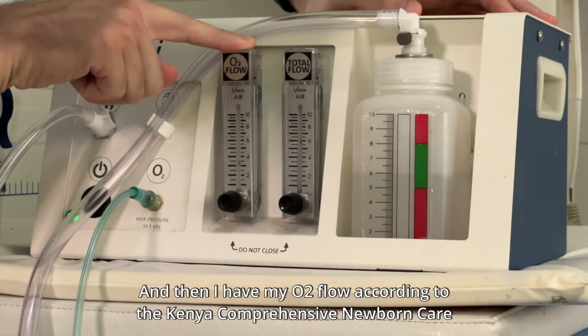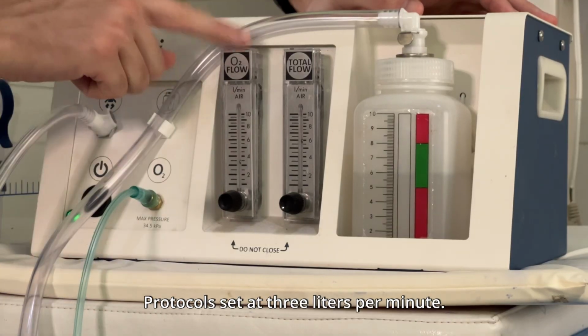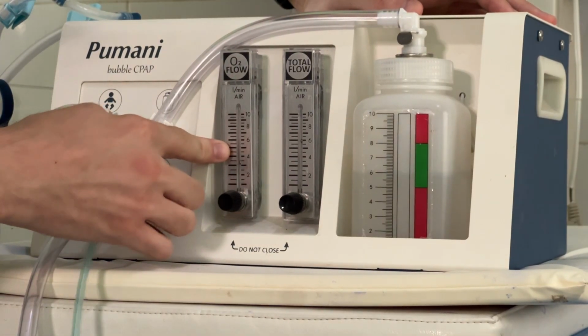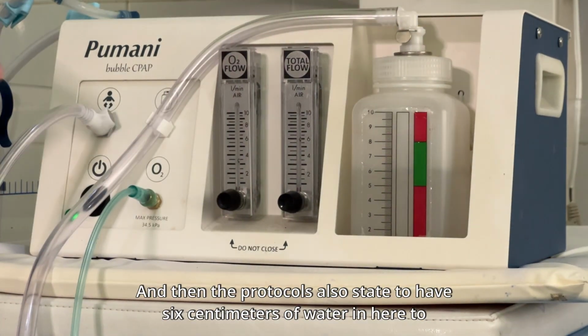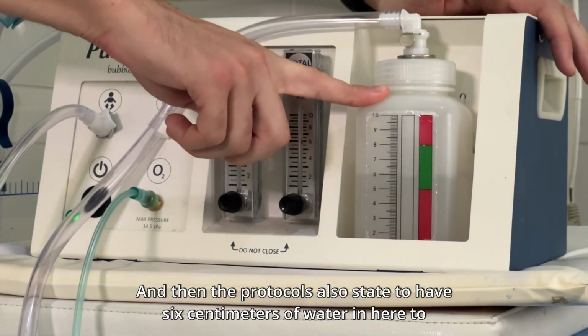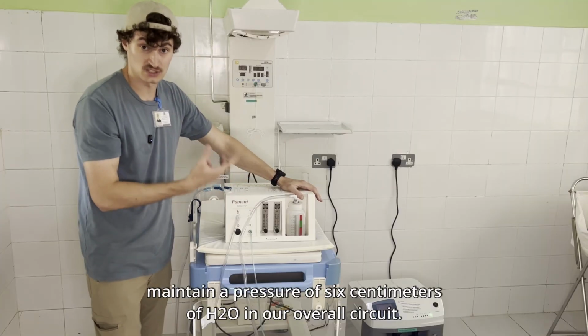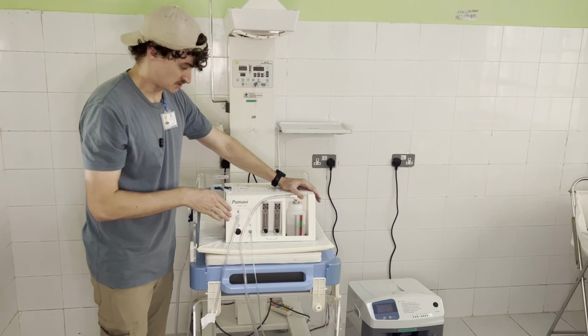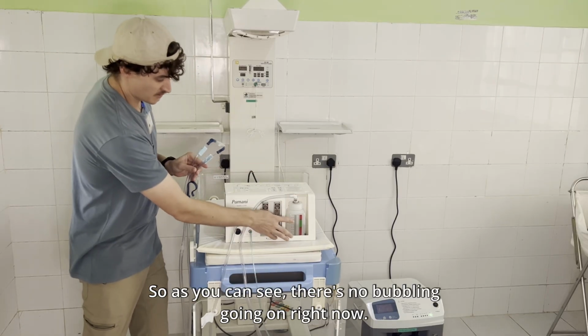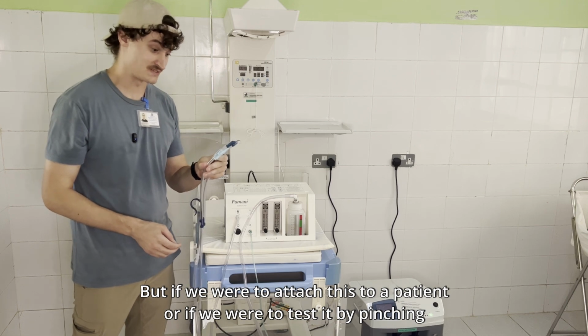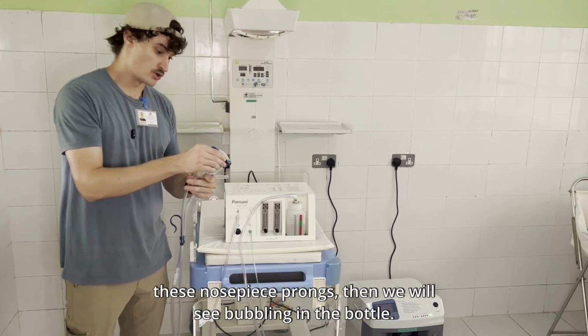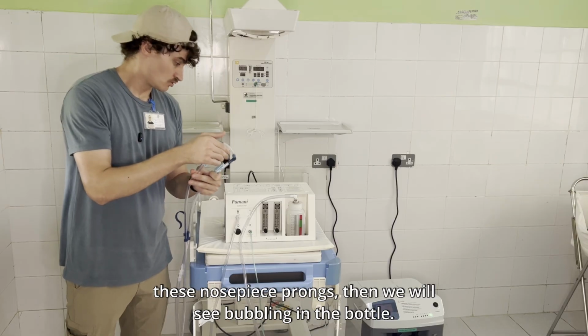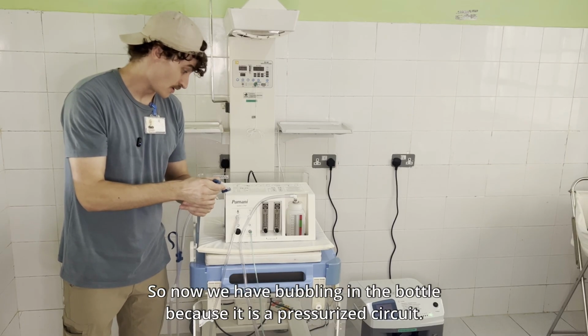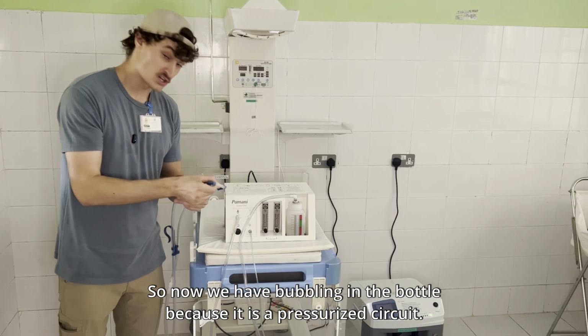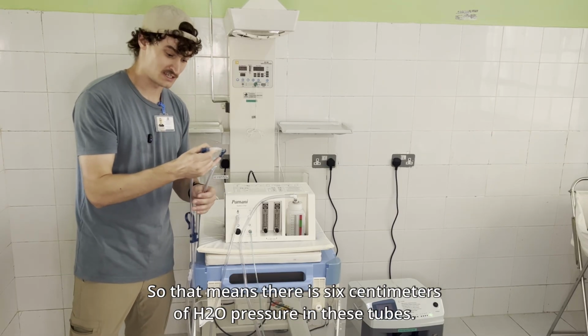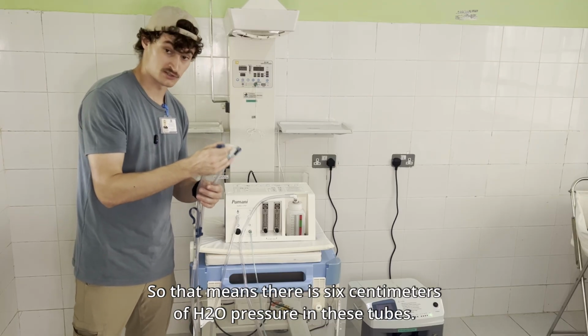And then I have my O2 flow according to the Kenya Comprehensive Newborn Care Protocols set at 3 liters per minute. So I have 6 right here, I have 3 right here, and then the protocols also state to have 6 centimeters of water in here to maintain a pressure of 6 centimeters of H2O in our overall circuit. So as you can see, there's no bubbling going on right now, but if we were to attach this to a patient or if we were to test it by pinching these nose piece prongs, then we will see bubbling in the bottle. So now we have bubbling in the bottle because it is a pressurized circuit. That means there is 6 centimeters of H2O pressure in these tubes.